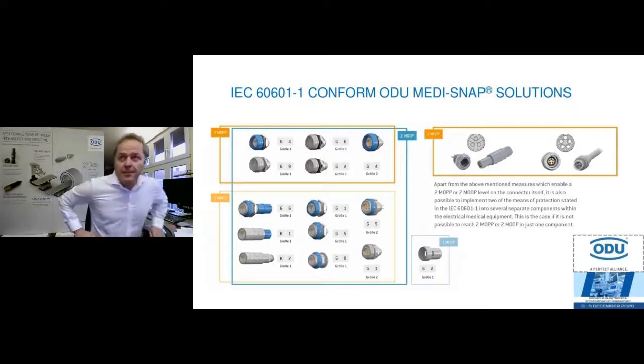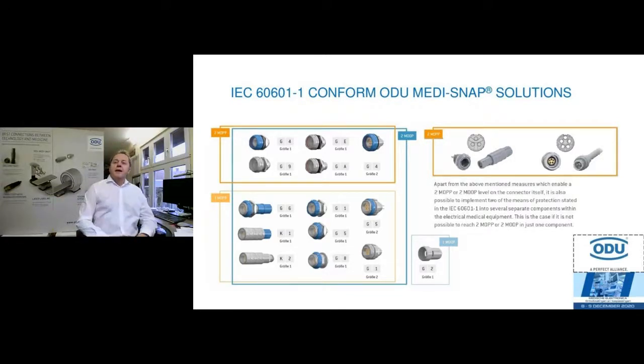On the next page, you can see existing connectors, which has the name MediSnap, which is right now conform with the IEC 60601. And I just want to explain a little bit more about this page. Above, on the left side, you see a receptacle which has right now 2 MOPP, meaning this is the protection to the patient, which is safe, which has this minimum 8 millimeters, but also 2 MOOP.